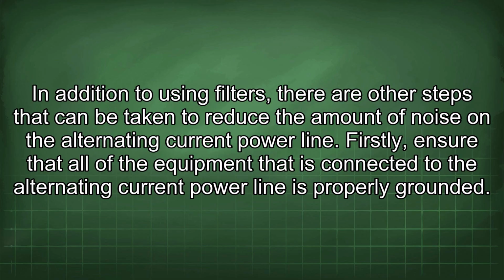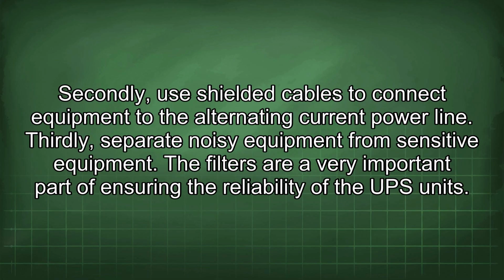In addition to using filters, there are other steps that can be taken to reduce the amount of noise in the alternating current power line. Firstly, ensure that all of the equipment that is connected to the alternating current power line is properly grounded. Secondly, use shielded cables to connect equipment to the alternating current power line. Thirdly, separate noisy equipment from sensitive equipment.